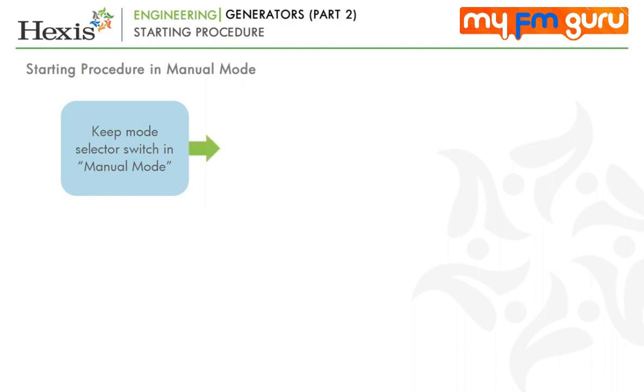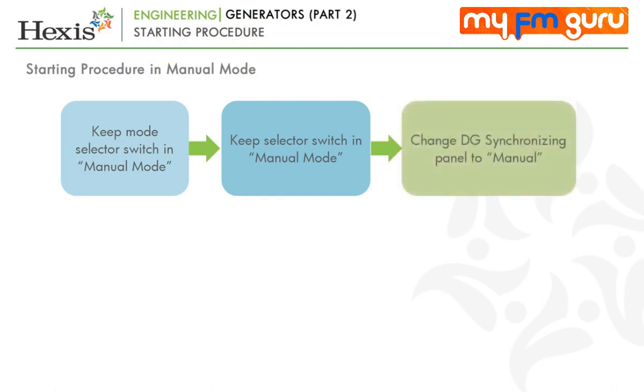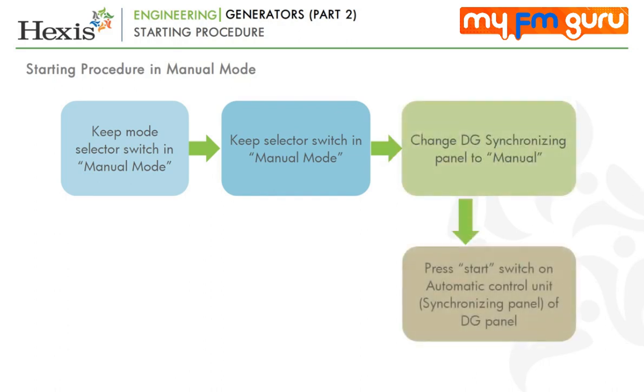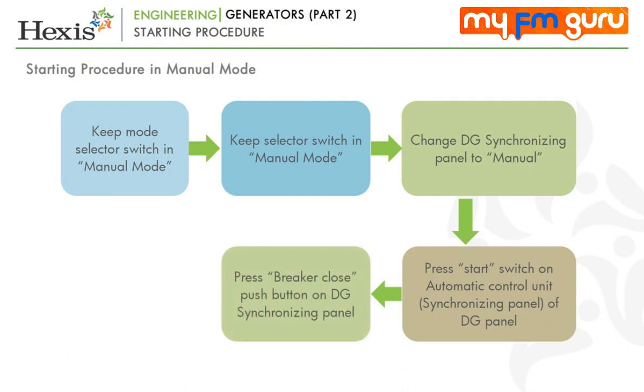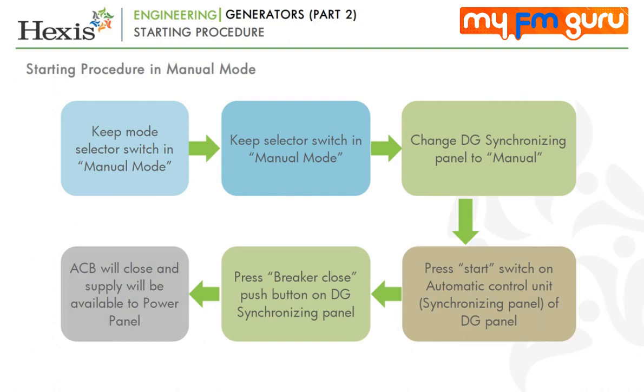Use the following steps given below to start the generator in the manual mode. Keep the mode selector switch in manual mode. Keep the selector switch in manual mode position. Change the DG synchronizing panel to manual. Press the start switch on automatic control unit, that is synchronizing panel of DG panel. Make sure that the voltage on main DG panel is 415 volts and frequency is 50 Hz. Press the breaker close push button on DG synchronizing panel. Note that the ACB will close and supply will be available to power panel.